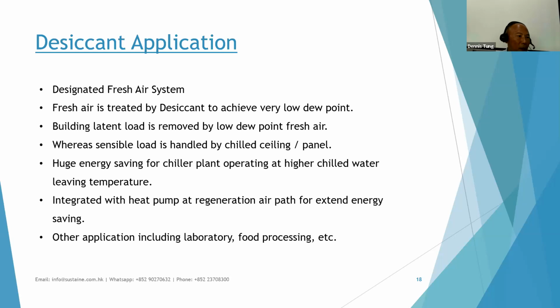If we can use an energy efficient method to operate a sensible-only air conditioning system, then we can save a huge amount of energy. For example, if we set the chilled water temperature at a much higher set point, we can save a lot of energy. So we try to use a desiccant method to reduce the water content in the air, particularly in the fresh air, because every location needs fresh air. So we can use fresh air to reduce the humidity inside a building, and the remaining sensible temperature can be achieved by a higher chilled water temperature operating system, and this will save a lot of energy for the building.